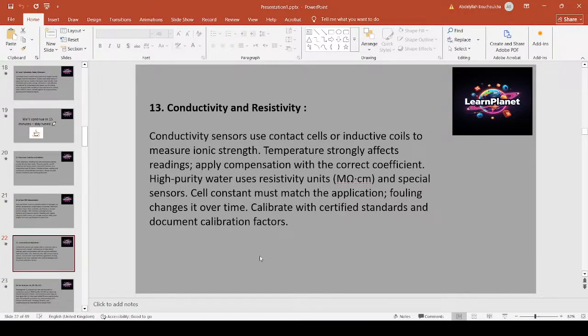Conductivity and resistivity. Conductivity sensors use contact cells or inductive coils to measure ionic strength. Temperature strongly affects readings. Apply compensation with the correct coefficient. High purity water uses resistivity units, megaohm-centimeters, and special sensors. Cell constant must match the application. Fouling changes it over time. Calibrate with certified standards and document calibration factors.